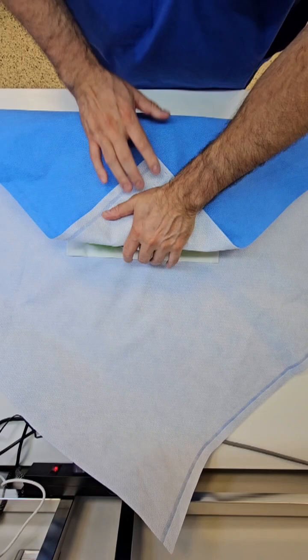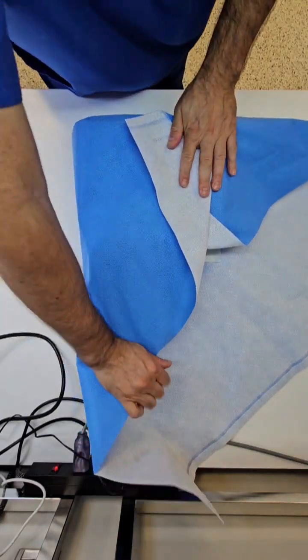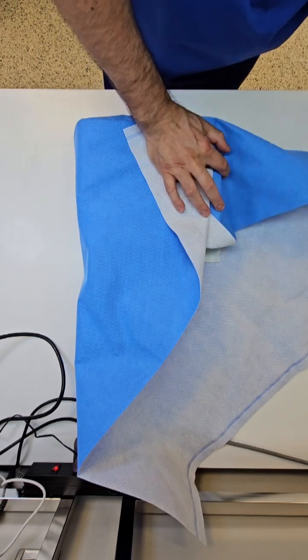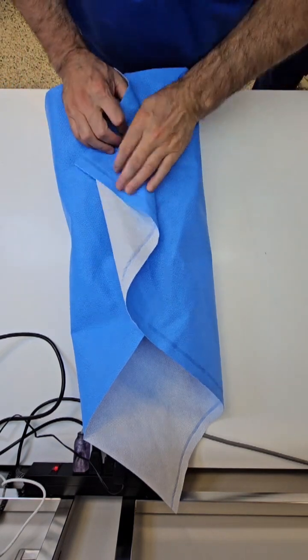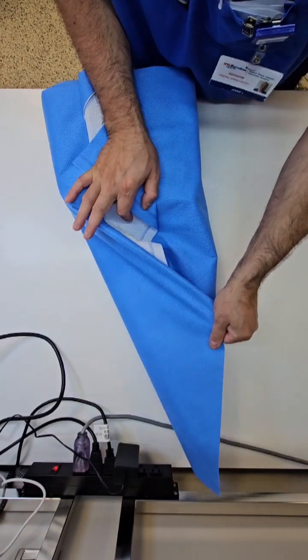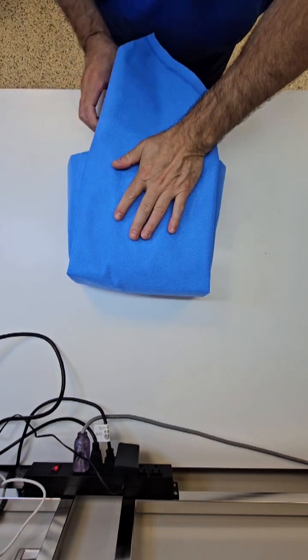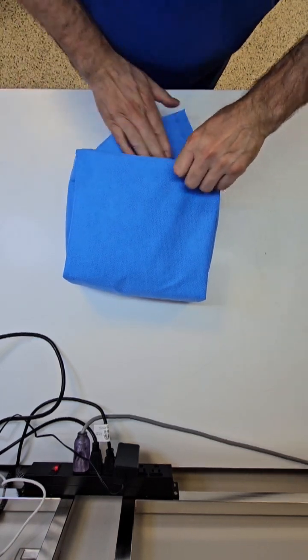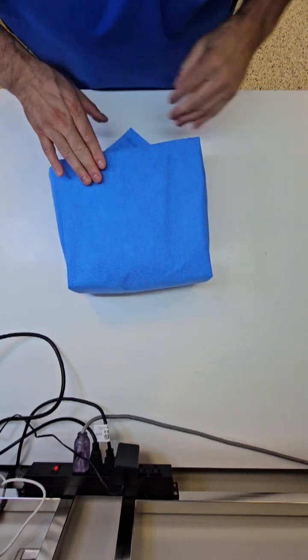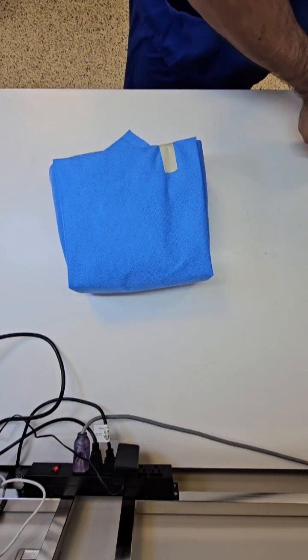There are other methods of protecting the medical device. This is the wrapping method, which uses a specialized material called SMS — spunbond, meltblown, spunbond material. There is a specific wrapping technique each technician needs to learn to protect the medical device from contamination. Contamination comes in forms of humans, the environment, dust, changes in temperature, and the microorganisms we produce that are all over the facility. We do not want these items contaminated before they're used on a patient, and that is how we protect them after sterilization.